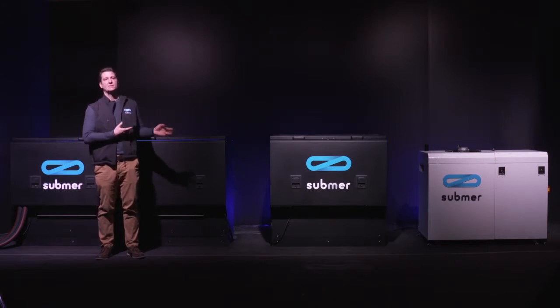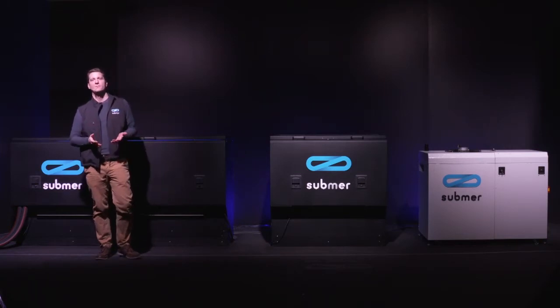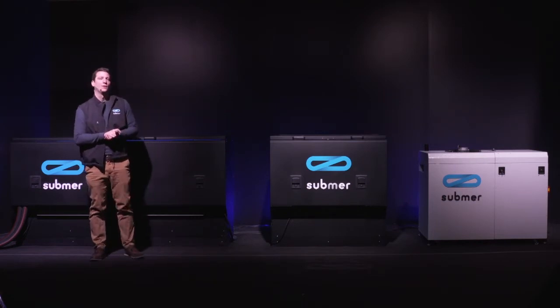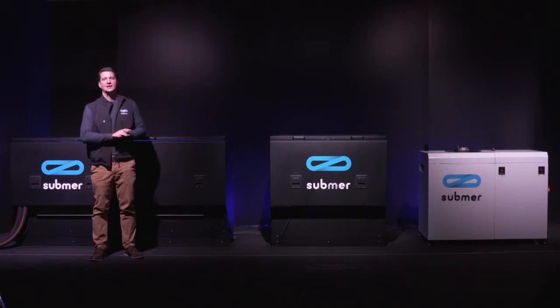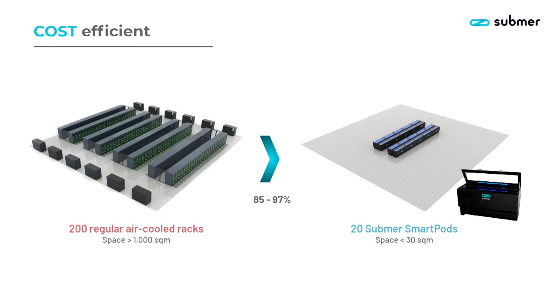But these systems in production, together with the secondary cooling that's required, they operate at a PUE of 1.03. So a massive reduction and really looking at getting that PUE right down to 1, which is the journey that we're on. And they allow us to increase substantially the density per square meter, because the smaller system can host up to 50 kilowatts of IT load. The bigger system, 100 plus. So we have configurations and deployments today that are in the range of the 100 kilowatts per tank. So without further ado, let's have a look.